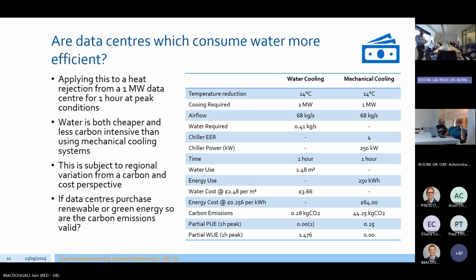Now, if we also consider the carbon emissions, if we take that water as potable water, in terms of, you'll correct me if I'm wrong, scope 1 emissions. Yes, is it? I can't remember. It is, depending on if you're the supplier or not the supplier. Okay, fair enough. So then the carbon emissions for potable water based on that amount of water is 0.28 kilograms of carbon, whereas the electricity based on the grid would be 44 kilograms of CO2 for that 1 hour. And again, looking at the partial PUE and the WUE, the figures there are based on those numbers. So water is effectively a cheaper and potentially more carbon efficient source of cooling.